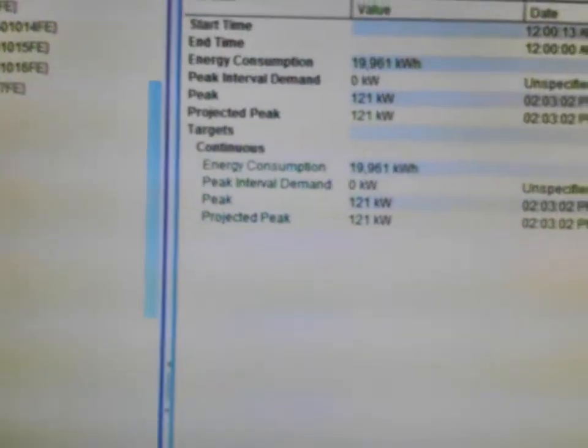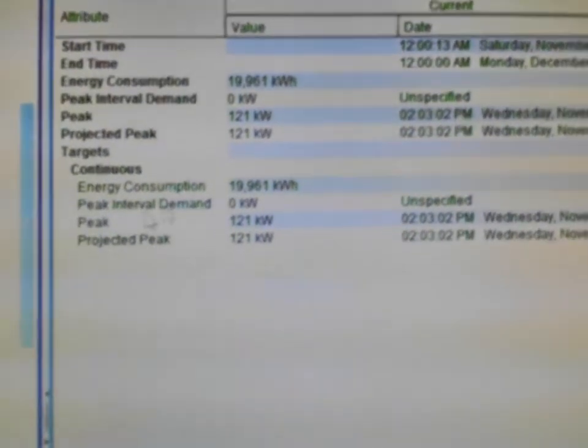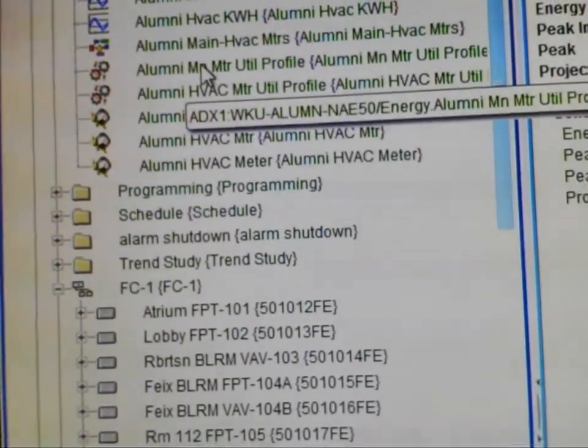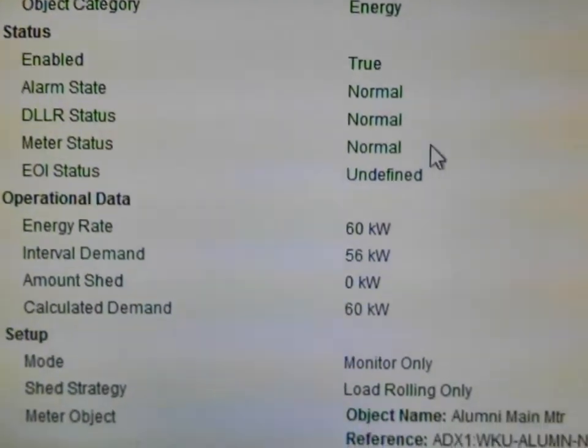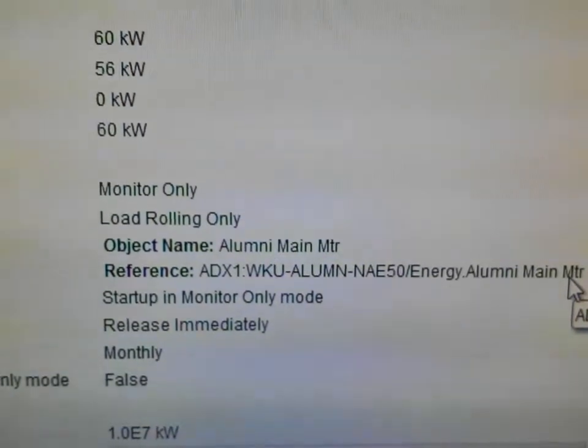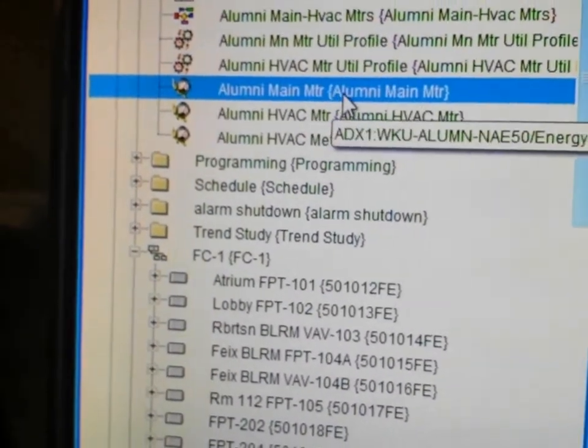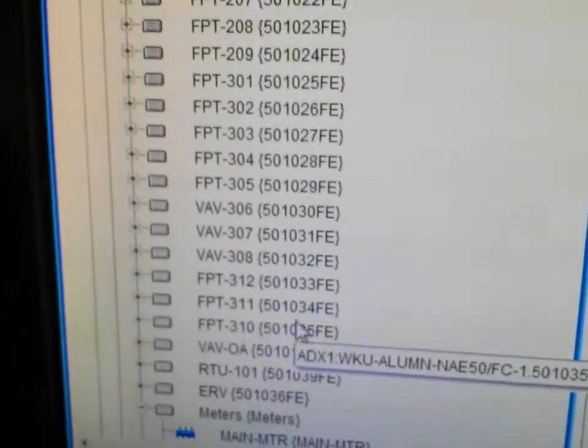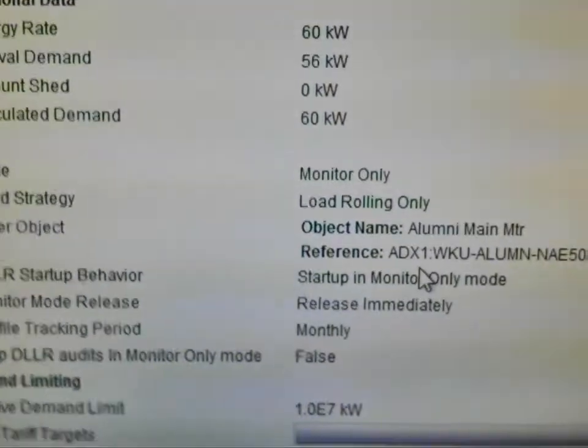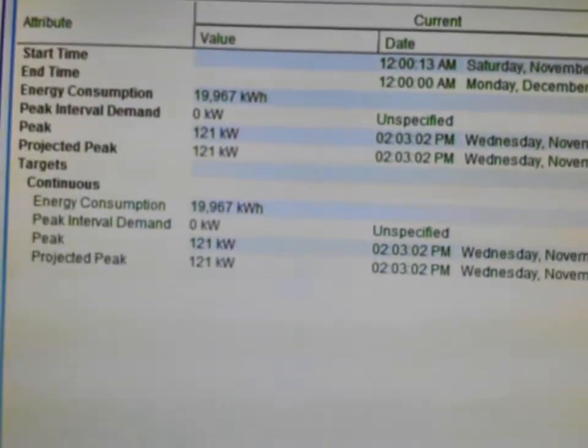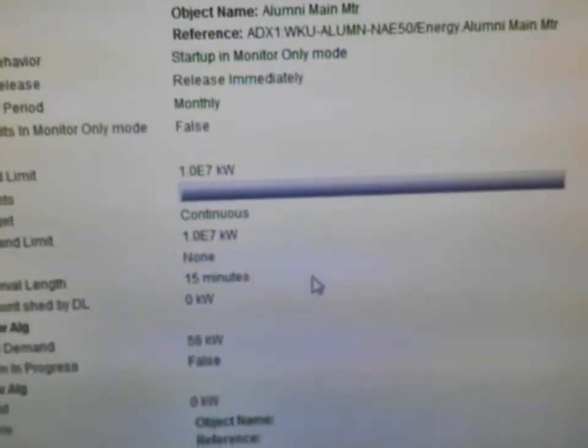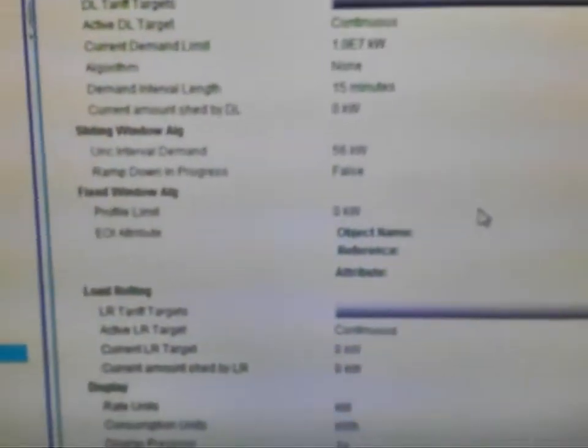If you want to set it up so you can see what you're doing throughout the month, the third object you will be inserting will be a DDLR, which is a data logger. We can see that here — this DDLR will be tied to that meter we were looking at earlier, and that meter is then tied to the accumulator. Once that information is pulled in, it will allow you to track usage for an entire month, or however you have it configured for your particular building or meter. This one is set up to run every month.